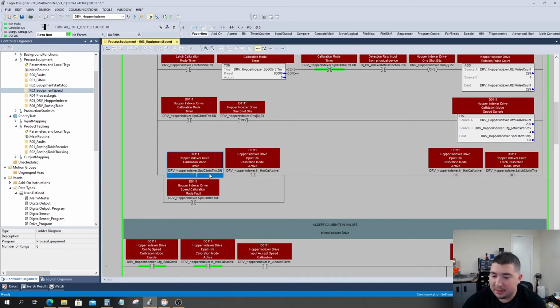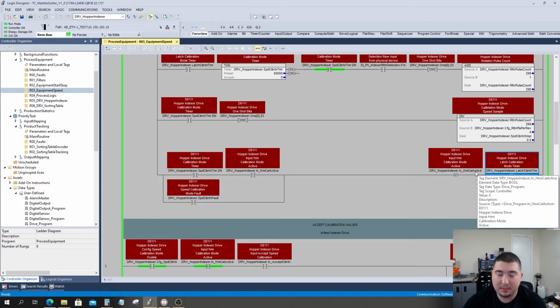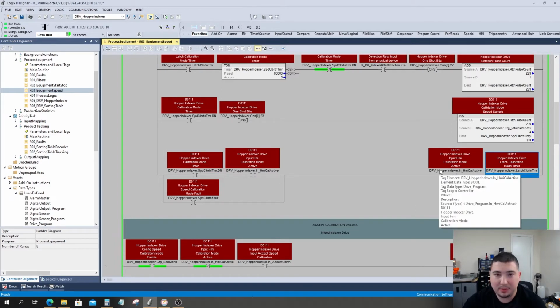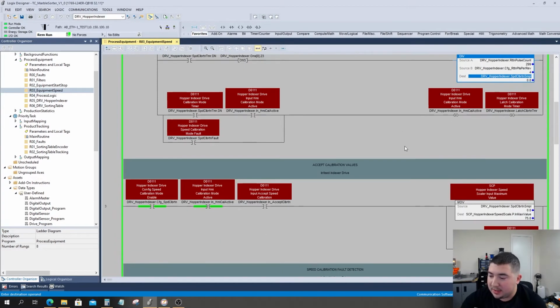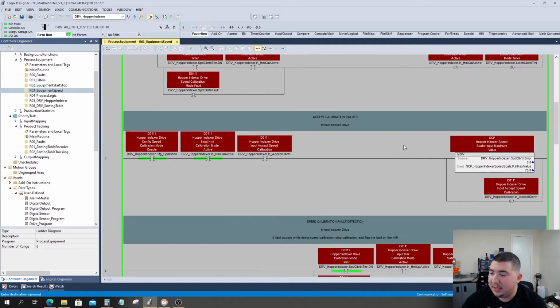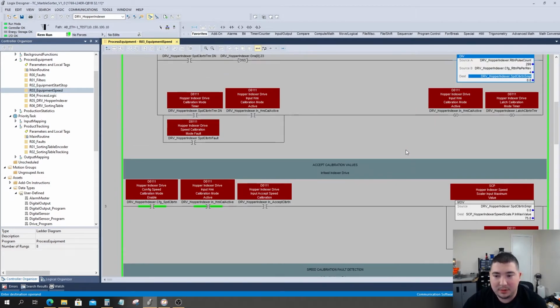The last thing down here is that after the calibration sample is complete, we don't necessarily need to keep the motor running, so we can go ahead and stop the current speed calibration mode. This will stop the motor, and it will also unlatch any other flags that have held this active during this time. Once that is complete, we can then determine whether or not we want to accept those values into the program.